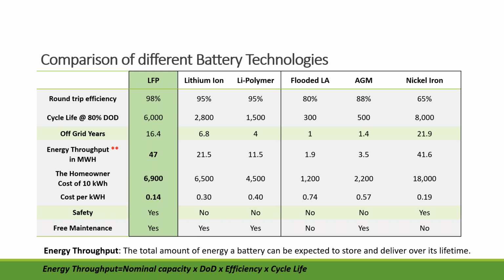Now at 80% DOD, that's the expected cycle life you can get from the different chemistries. LFP is number 2. Nickel iron is very good, at 8,000 cycles. And in terms of off grid years, it's basically, if you do one cycle a day, how long that battery can last. LFP can last 15, 16 years. Flooded AGM, if you discharge it 80% every time, you're talking about year 2. In reality, I know that a lot of people probably will not go over 50%, and that battery can last longer.